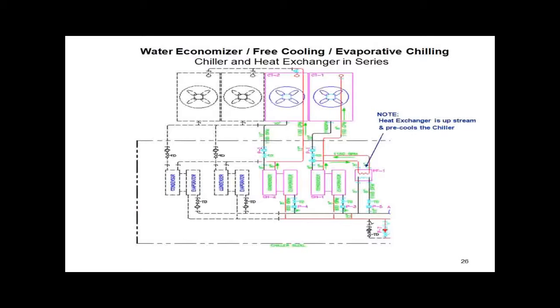Here's a last little example of a typical layout of 4 chillers and 4 towers. And the message is, again, because this is the big message I want you to get: you may need 2 sets of pipes out to the towers, back to the chillers. Real fundamental statement. People are just not used to thinking that way.